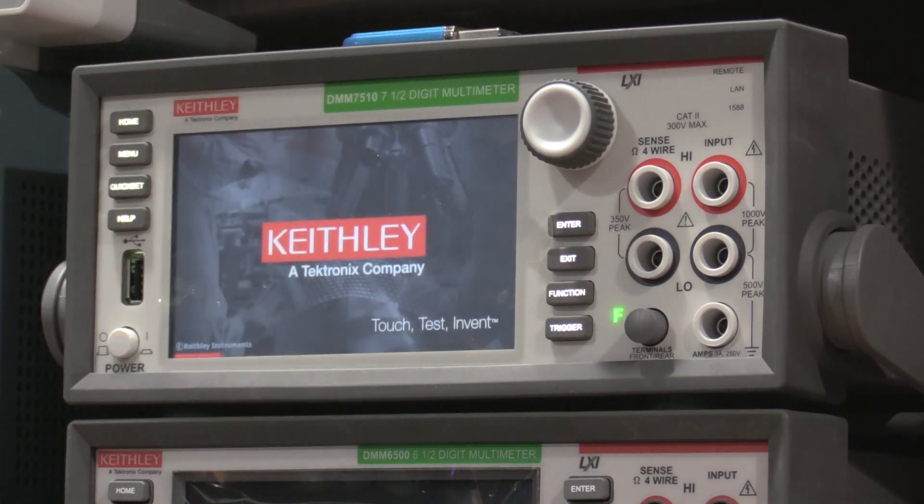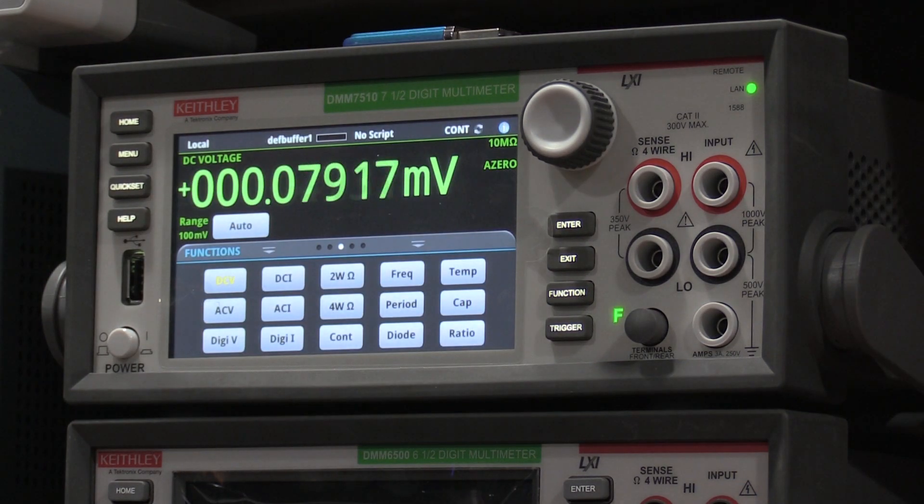It's taking a minute. There it goes. Based on that update rate, I can say my settings have been blown out, which isn't too surprising given that one of the things Keithley does when you send a meter off is they update the firmware to the latest unless you tell them not to. So with the firmware update I'm going to have to set up some things. The update rate is absolutely insanely fast — that's not a trick of the camera, that's really how fast the meter's cranking. That won't be useful long term because it's not at its highest accuracy when it's moving that fast.